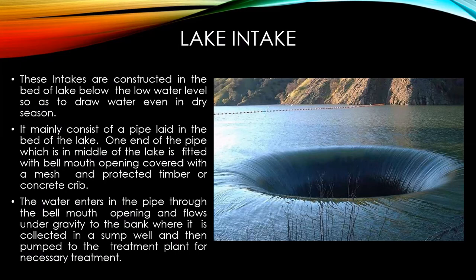What are the components? One, you have a pipeline connecting the lake to the treatment plant. Two, the bell mouth opening where water enters the pipeline. This will be the second component. And the bell mouth opening is protected with concrete crib for support. The water enters in the pipe through the bell mouth opening and flows under gravity to the bank where it is collected in a sump well and then pumped to a treatment plant for necessary treatment.